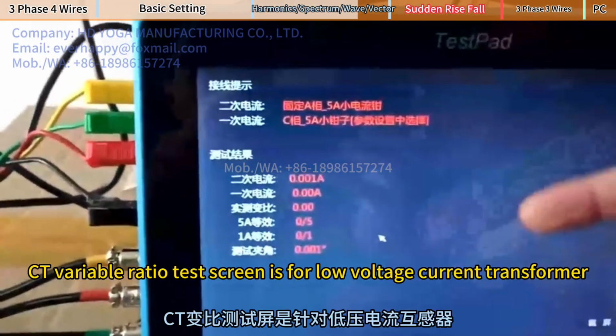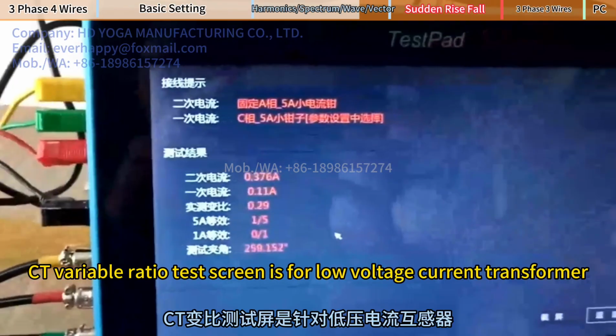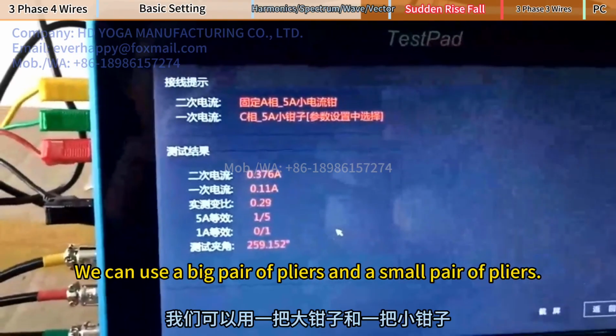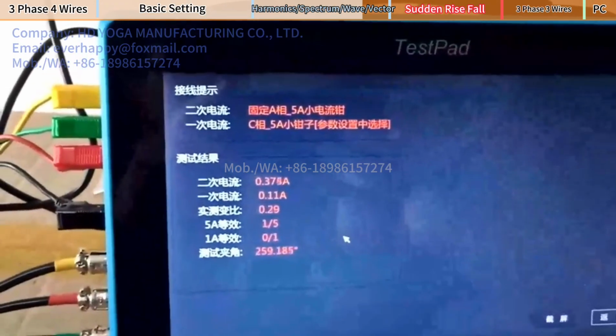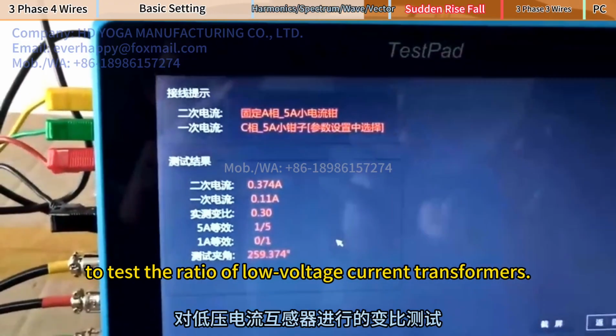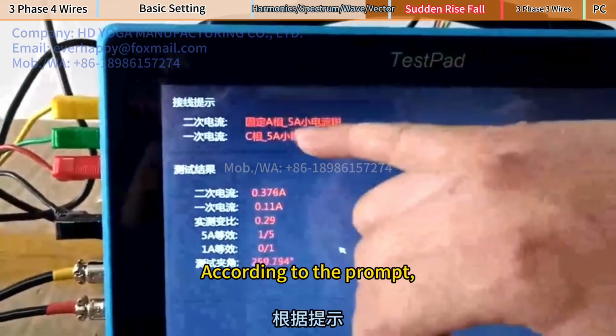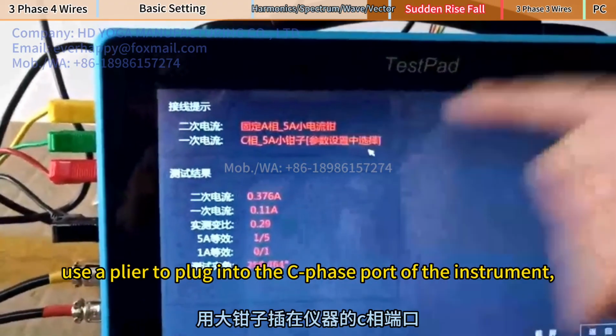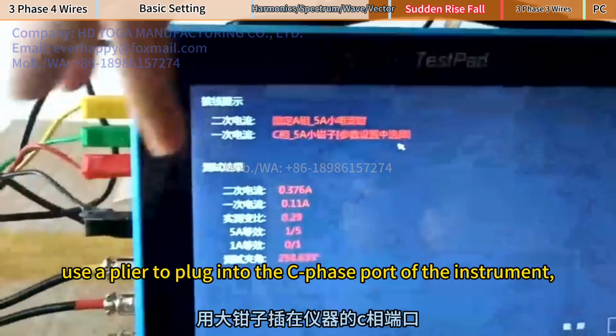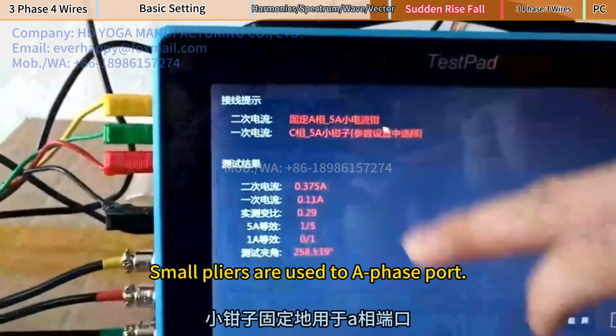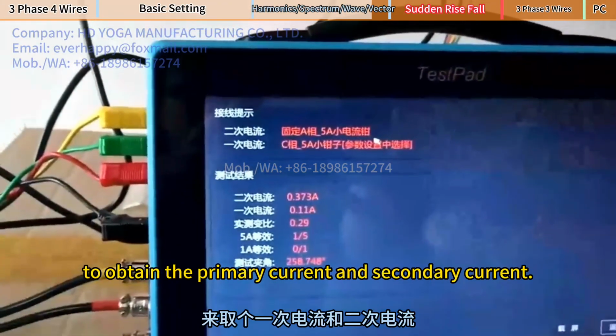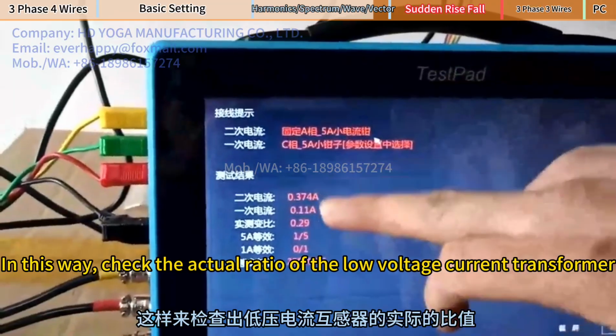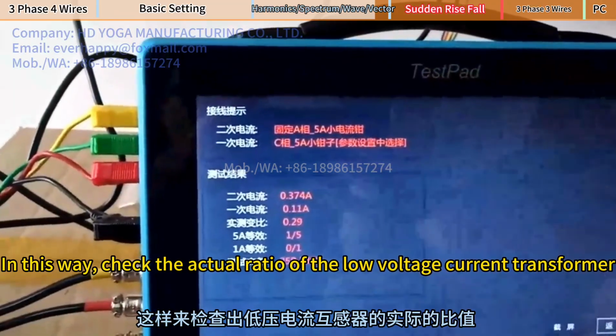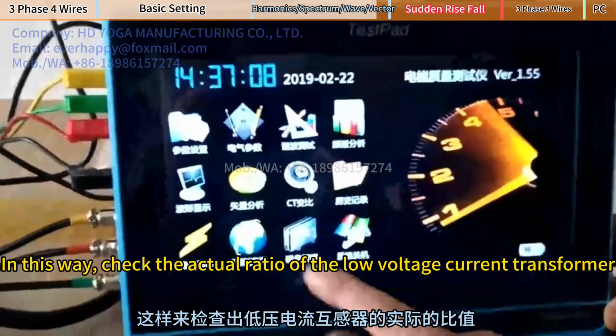The CT variable ratio test screen is for low voltage current transformers. We can use a big pair of pliers and a small pair of pliers to test the ratio of low voltage current transformers. According to the prompt, use a big plier to plug into the C phase port of the instrument. Small pliers are used for the A phase port to obtain the primary current and secondary current. In this way, check the actual ratio of the low voltage current transformer.